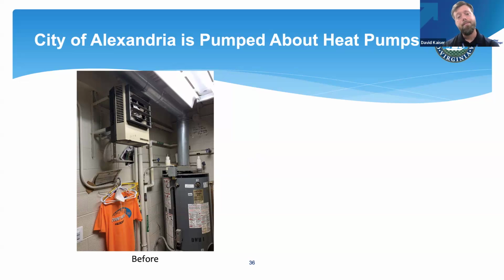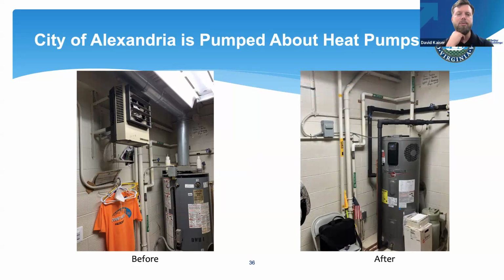So they felt that they needed to put electric resistance, or a heater of some sort, in there, given risk tolerance and that kind of stuff. However, what that did provide us, if you go to the next slide, please, is that we were able to remove that electric resistance heater because we could close up that vent if we put a heat pump hot water heater in there. So we closed up the flue pipe, no penetration now in the ceiling, no air can go in and out. And then we added some interior vents to the doors into that mechanical room so that now the conditioned space from the surrounding areas can enter the mechanical room, so it doesn't have to be an isolated room per the manufacturer's recommendations.